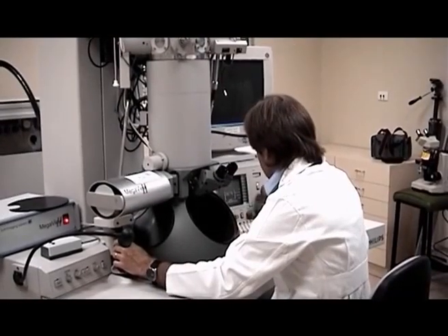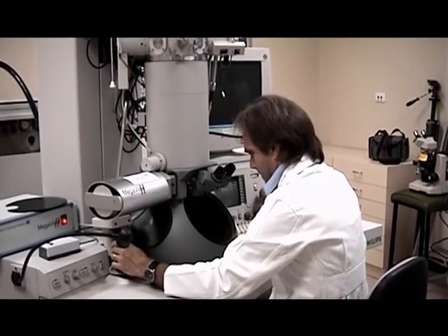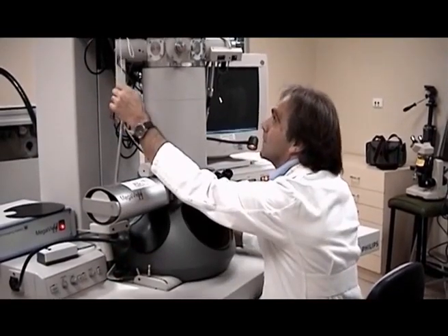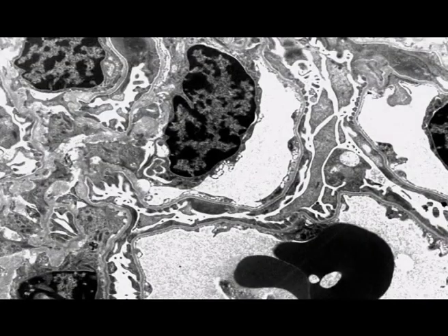The section can be viewed either by looking at the fluorescent screen in the microscope or by viewing at the monitor. At 1000 times magnification, the mesh of the grid and cellular outline can be seen. At 10,000 times magnification, the structural detail is very clear. At 25,000 times magnification, cytoplasmic details and membranes can be seen.